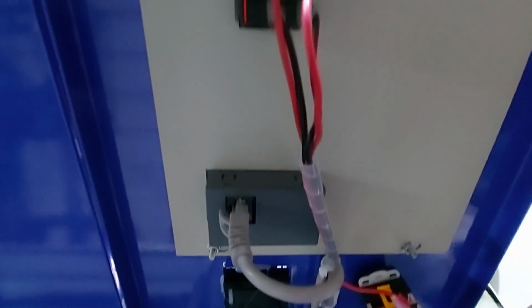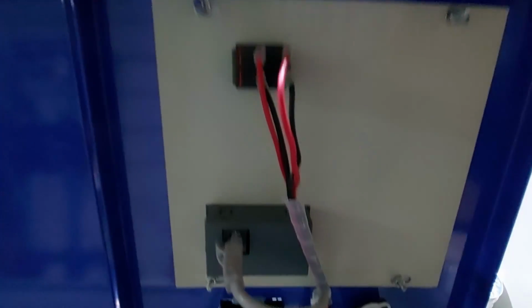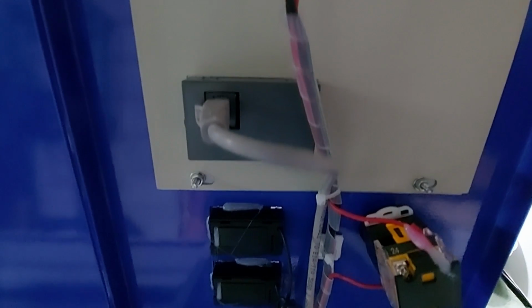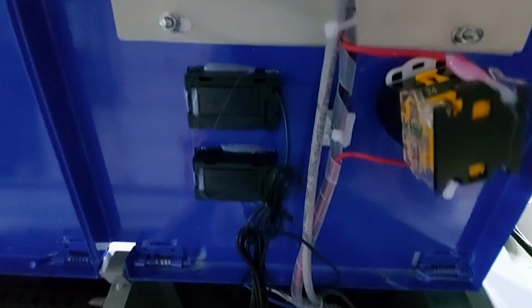Then I'm just going to inspect the whole machine. By the way, I do put a couple drops of Tetra, which is an algicide, in the water, and a couple drops of Dawn dishwashing liquid as well, which allows the air bubbles to evacuate the tube very quickly. You won't have any air bubbles if you do it that way.